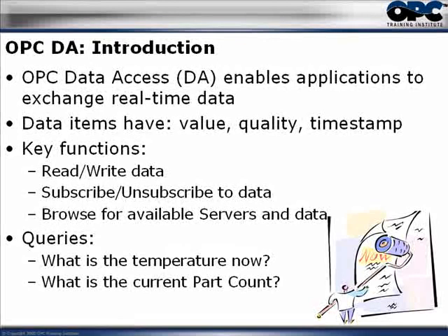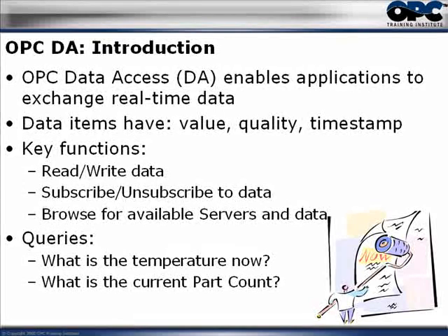An OPC client can ask many questions of an OPC server — for example: what is the latest temperature outside right now? What is the RPM of the feed water pump? How many cogs did we make today? These all boil down to one single question: what is the latest value you have? OPC DA is used for real-time values only; if you want a previous value, you must use the OPC Historical Data Access specification.